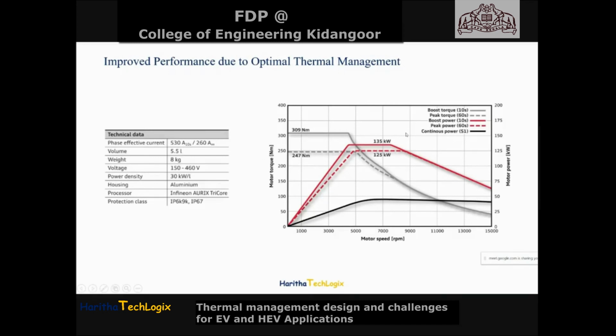You can very clearly see that the boost, meaning the peak torque ability of the motor, is around 247 Newton meters for up to 60 seconds. And the boost torque capability of this motor is around 10 seconds, where it can provide more than 300 Newton meter torque.